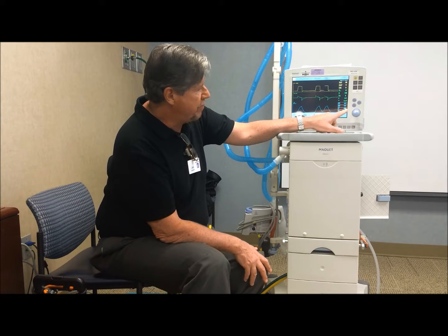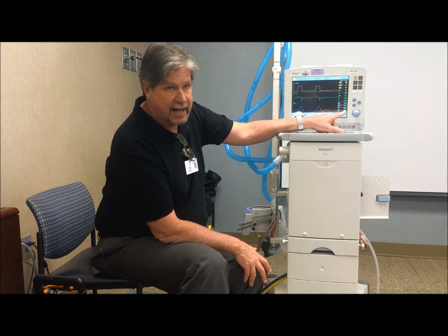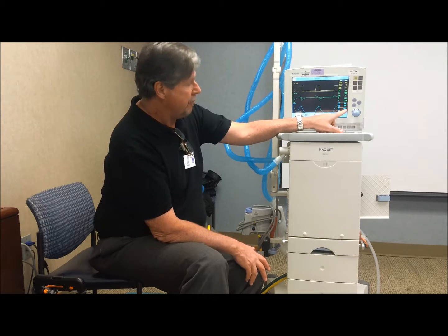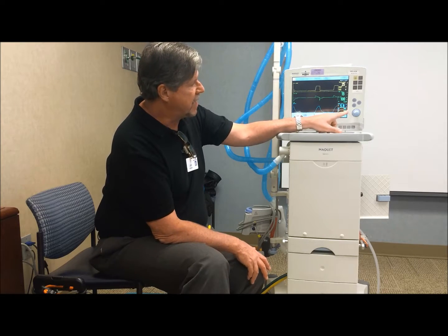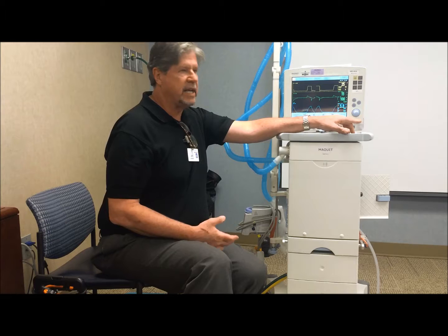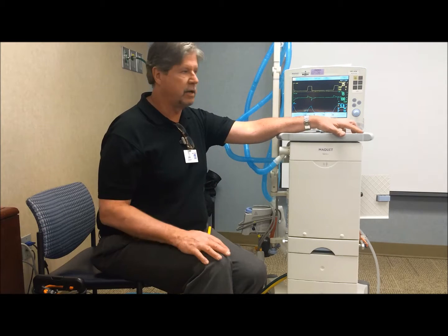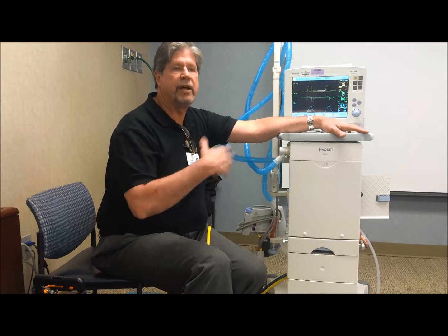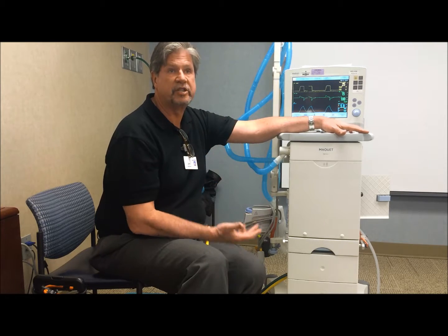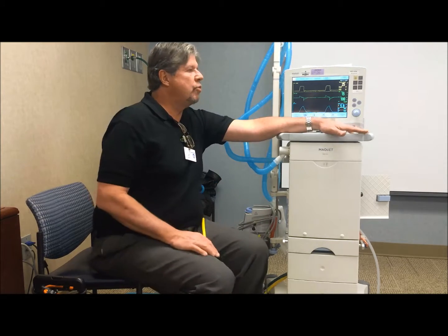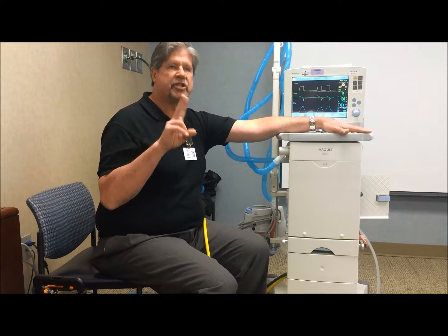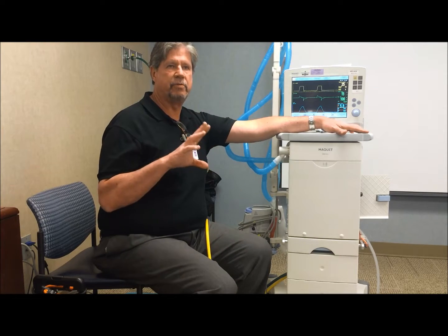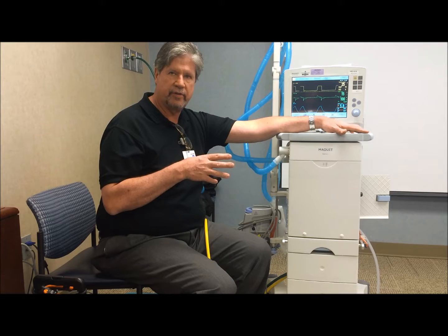In reality, we'd be delivering 400 and exhaling 400, but in some cases with Heliox, you might see 200 cc's coming back and you go, oh my goodness, we got a leak. But you don't really have a leak, it's just that the measurement system is posting an erroneous number. So we basically have just those two issues when it comes to using Heliox with a ventilator.